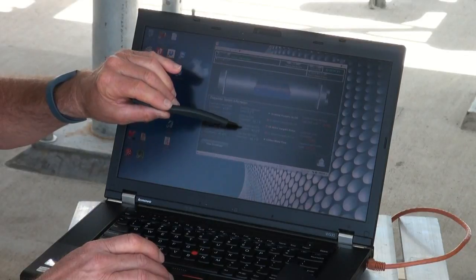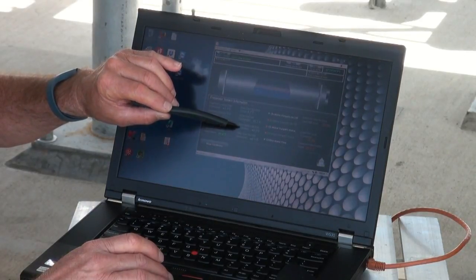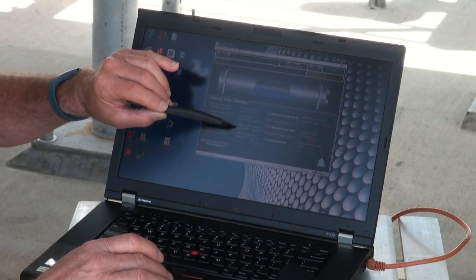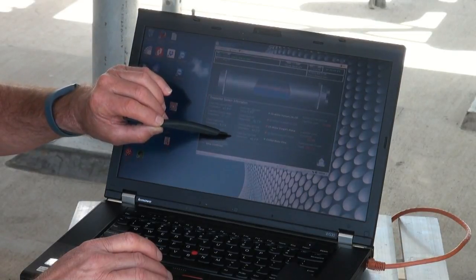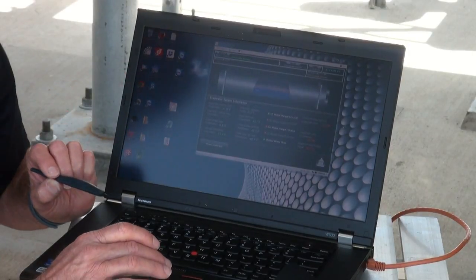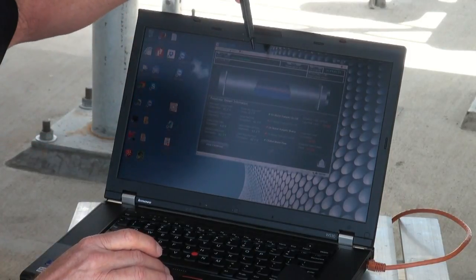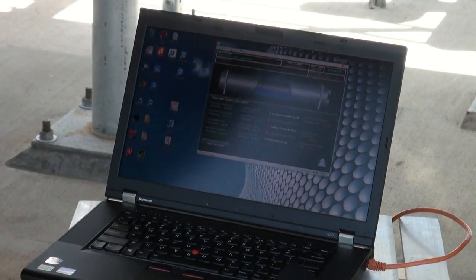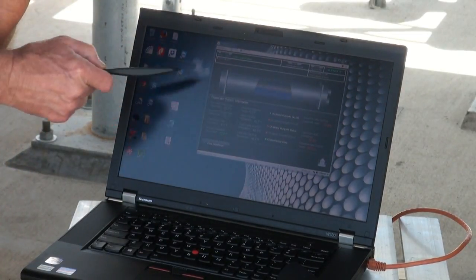It shows the active set point, and then here you've got the chiller enable set point, 43.2. So it looks like roughly 1 degree above set point the chiller will start. Then you have a stop set point of 40. So 2 degrees below set point, you'll start to cycle compressors off. I don't know if we're controlling pumps with this controller or not, but you can see we have the LEDs here that give you indication of which pumps are enabled.